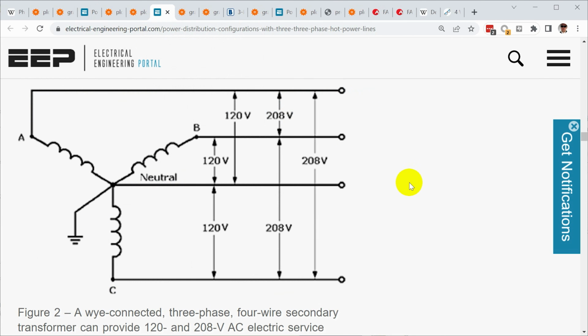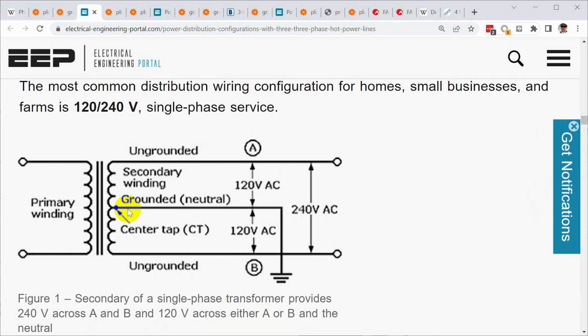And the answer is it depends. There are a bunch of different ways that three phase power is provided and wired into buildings. The most common that you'll find here in North America is called the Y configuration, often just spelled WYE, but it's in the shape of a Y. And you have three phases of power, A, B, and C, and a neutral. So you've got four lines plus a ground. The neutral is ground referenced, just like it is in the 240 volt split phase.